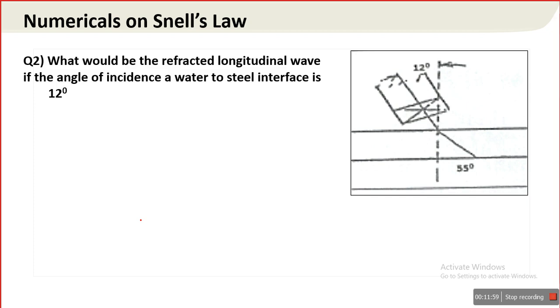So second numerical, what would be the refracted longitudinal wave if the angle of incidence at the water to steel interface is 12 degrees? So the angle of incidence is given, and we need to calculate the other angle, which is the refracted longitudinal wave angle.